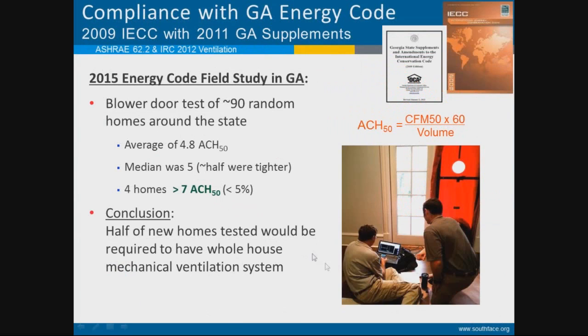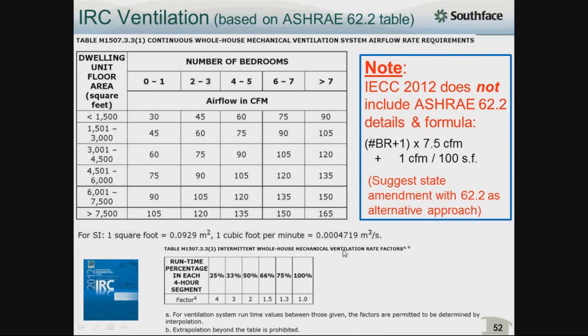We have a question from ASHRAE Standard 62.2. The Q of the fan equals Q total minus the Q infiltration. Basically, in the ASHRAE standard, the nature of this question, I'm gathering, is you get infiltration credit if you just use the ASHRAE standard. The code doesn't go into that level of detail. They just do a simplified version of it. Right. And I'm reading the rest of the question here. Basically, making tighter buildings means you get less infiltration credit. And the person is asking, this suggests there's actually a penalty for making buildings tighter. You advocate that Standard 62 should be ignored.